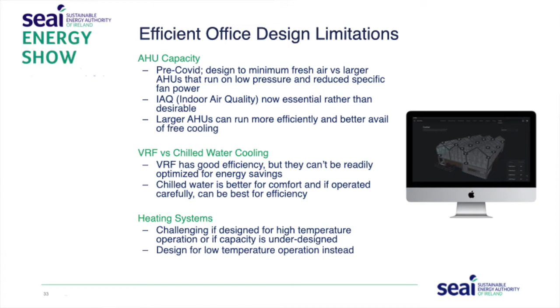I mentioned design limitations, not just office, but any building in particular, and this dash to minimum fresh air, so we do have a little bit of a challenge out there. A lot of more modern buildings in the last couple of years have been built with smaller air handling units than ideal, which means they can't really cope with the increased ventilation you want for COVID. On the one hand, they also can't increase to give free cooling when the outside temperature is suitable. Whereas if you had a larger AHU, you could always scale it down, make it run slower. Actually, a big fan working at a lower speed uses very little energy. So you can take a bigger unit, run it slower, and then if you have a situation where higher ventilation rates are required, you can ramp that up. So you got tremendous flexibility and tremendous possibilities for energy efficiency.